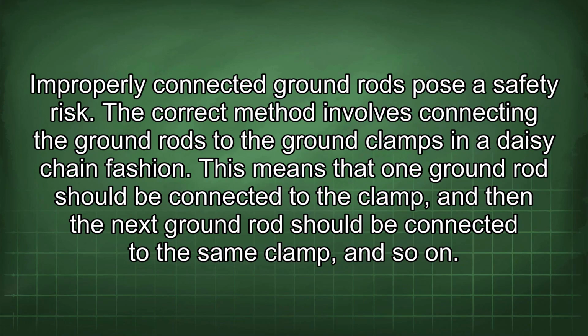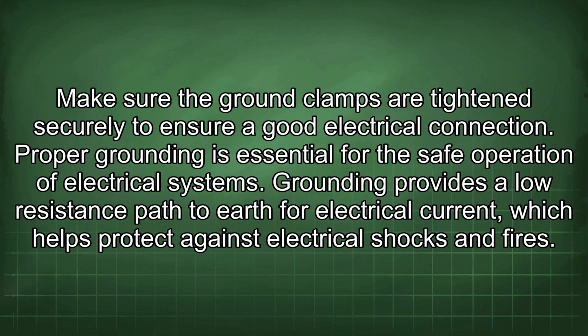Improperly connected ground rods pose a safety risk. The correct method involves connecting the ground rods to the ground clamps in a daisy chain fashion. This means that one ground rod should be connected to the clamp, and then the next ground rod should be connected to the same clamp, and so on. Make sure the ground clamps are tightened securely to ensure good electrical connection.